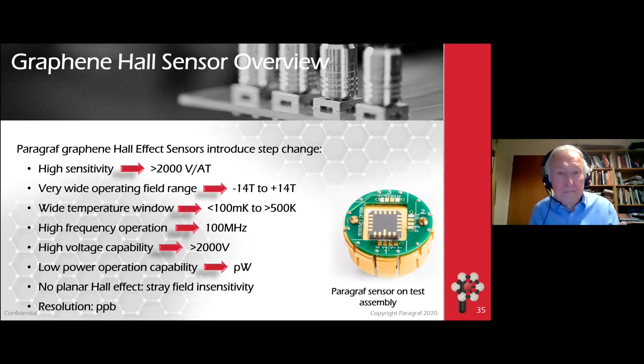Now, we've been comparing our Hall sensor with other Hall sensors. This is a comparison of not only our Hall sensor with other Hall sensors, but also with flux gates and with nuclear magnetic resonance machines, which are the other ways you can measure magnetic fields. If you look at the top line here, typical silicon Hall sensors, used in cars, have a maximum resolution in a 1 Tesla field of about 100 parts per million. The gallium arsenide-based Hall sensors, 10 parts per million. There's also a specialist Hall sensor, which is actually worse in resolution. Flux gates are very high. NMR probes are very high.